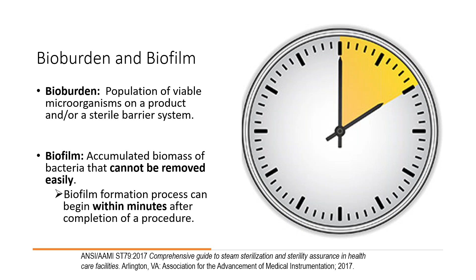And that formation of bioburden is particularly problematic in devices with lumens that are high in complexity, like our Da Vinci, again, laparoscopic, our orthopedic, all those. They're very intricate instruments, and biofilms are going to pose major problems for those, because once that biofilm develops, only direct friction or an oxidizing chemical can remove it. So prompt cleaning reduces or eliminates the population of biofilm forming microorganisms, which is going to be huge for your reprocessing department.